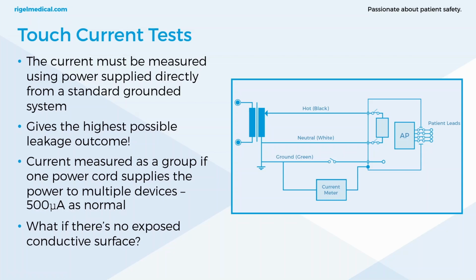Now, one query I sometimes get about touch current tests or enclosure leakage tests is, what if there's no exposed conductive surface? It can be simulated by placing a 10 by 20 centimeter metal foil in contact with the exposed surface, and then that is considered the exposed surface of the appliance, and all appropriate tests shall be performed on that foil using either a crocodile clip or any type of thing that's going to contact that foil as you would test it normally.